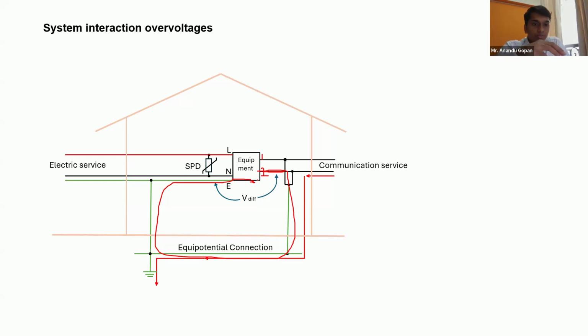What happens is, if your equipment is not rated properly, or if there is a huge surge incoming through your communication service line, this part will face an insulation failure - basically there will be a spark over from the port to the earth.